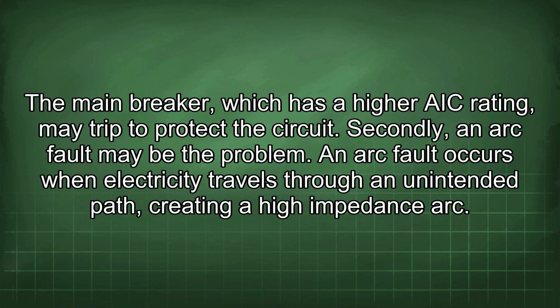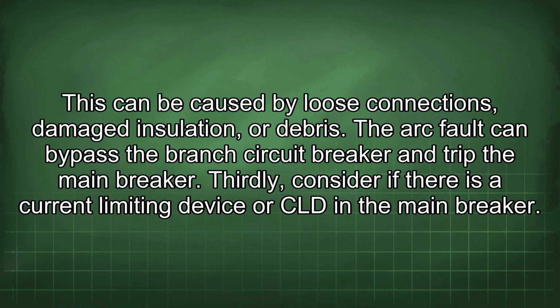Secondly, an arc fault may be the problem. An arc fault occurs when electricity travels through an unintended path, creating a high impedance arc. This can be caused by loose connections, damaged insulation, or debris. The arc fault can bypass the branch circuit breaker and trip the main breaker.